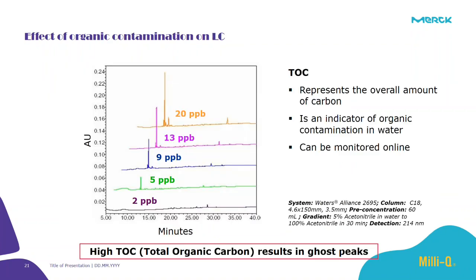So the effect of total organic carbon. What is total organic carbon, or TOC? It represents the overall amount of carbon. It is an indicator for organic contamination in the water. It can be monitored online also. So in this graph, you will see the effect of the concentration of total organic carbon in the water you are using in the analysis. High total organic carbon results in ghost peaks, as you can see from the graph.